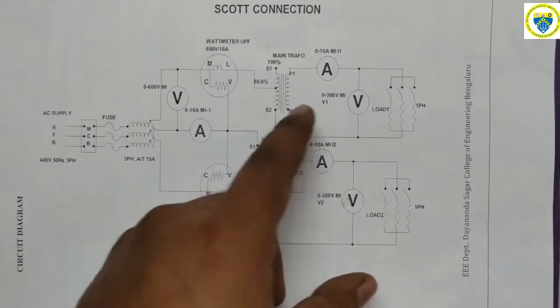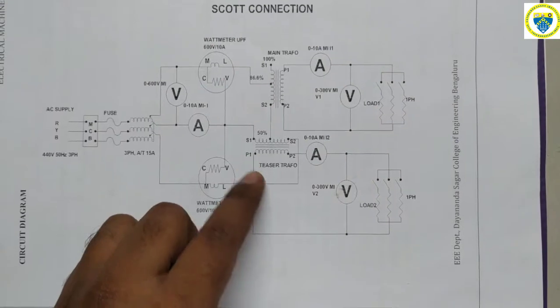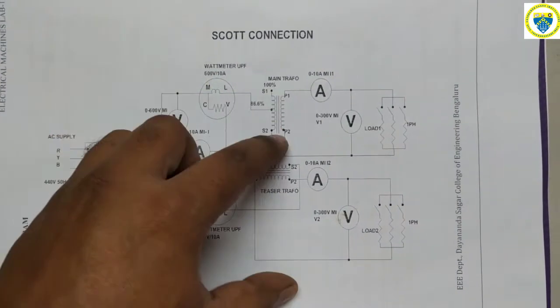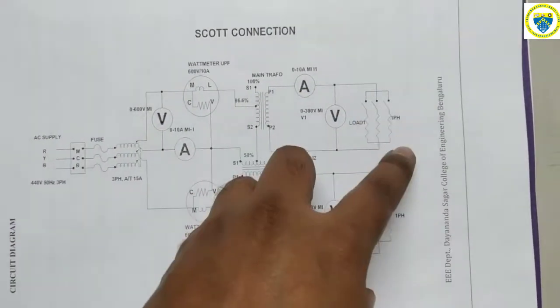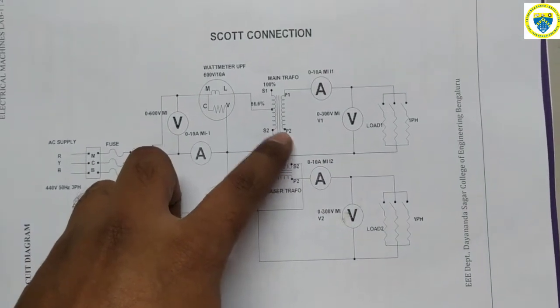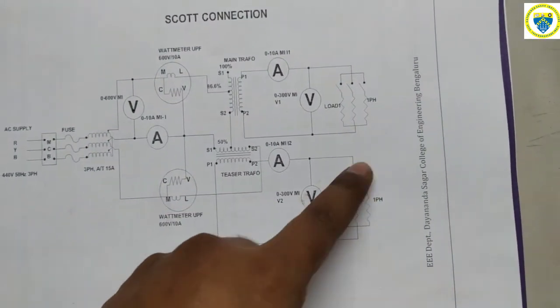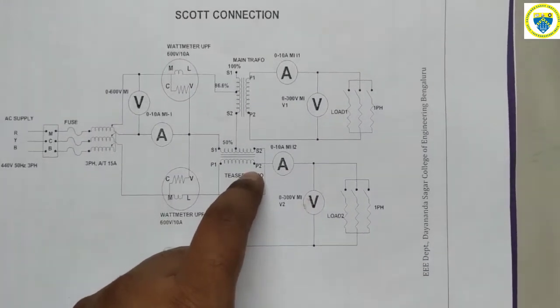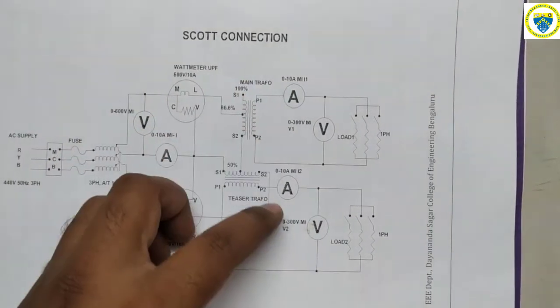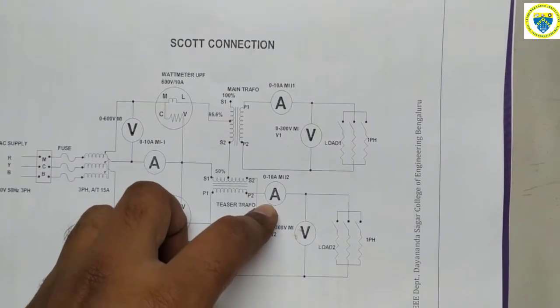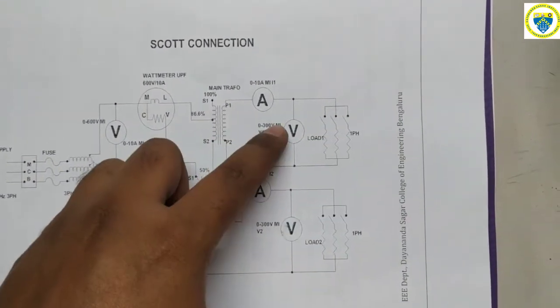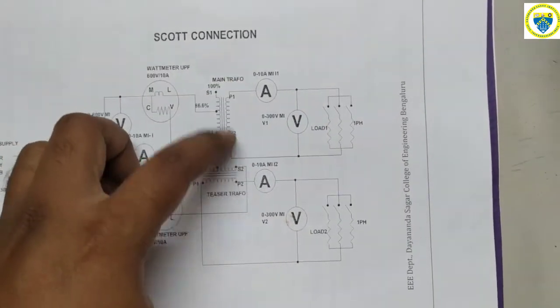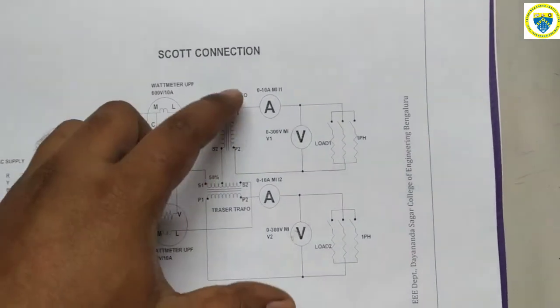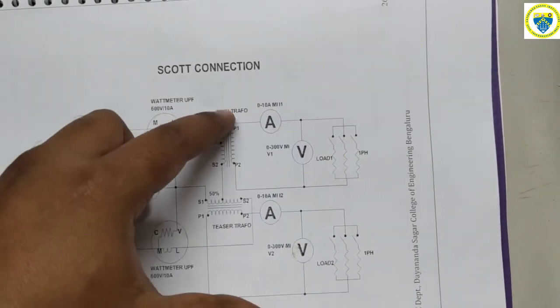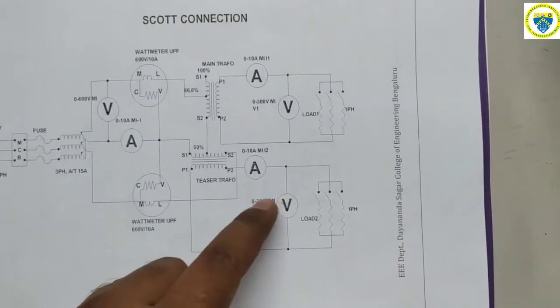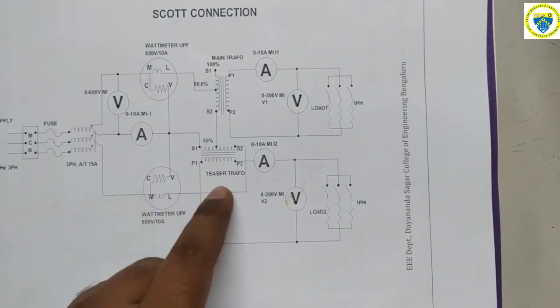Now let's see how exactly the loads are connected to the primaries of the main and teaser transformers. So P1, P2: from P1 to ammeter to load, again load back to P2 of the main transformer. Again similarly, from P1 to load, again load back to ammeter to P2 of the teaser transformer. We'll see. So again we'll be using ammeters to measure the current drawn by each load, and the voltmeter we can connect across the load, or we can connect across P1 P2 also. Now for our case, we will connect both the voltmeters across P1 P2 of the main transformer, and one more voltmeter across P1 P2 of the teaser transformer.